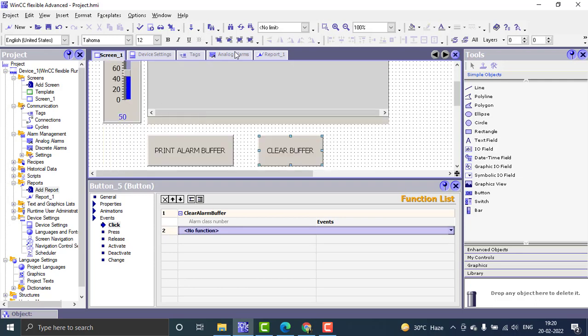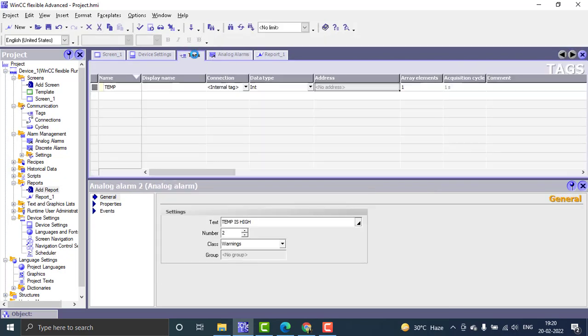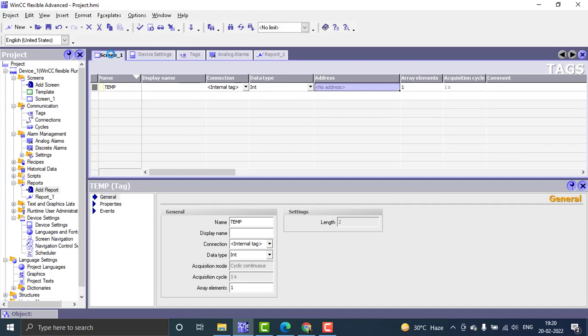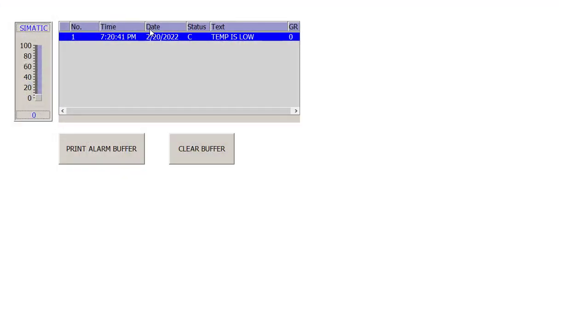Everything looks good in the report, alarms, and tags. Now I start the runtime to test. In the runtime screen, the temperature low alarm has already been triggered because the value is zero — which is below the limit of 20.